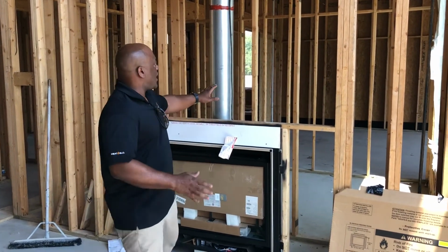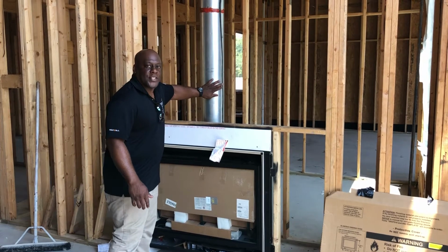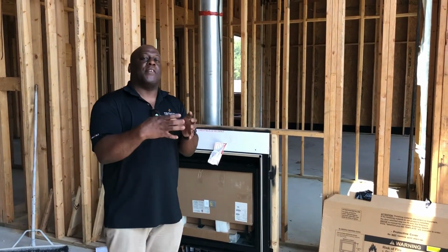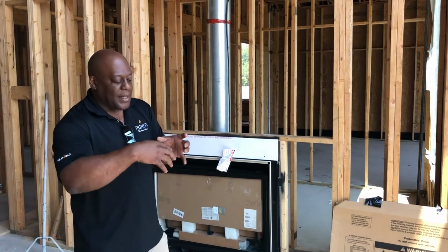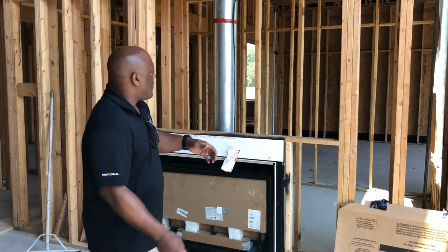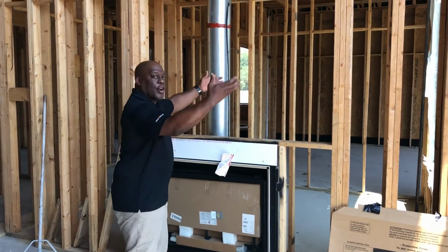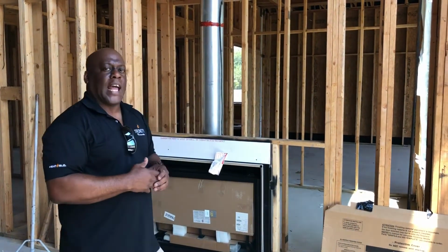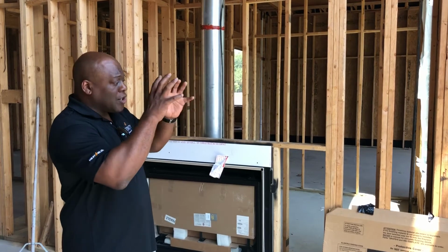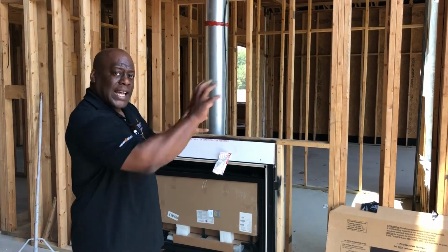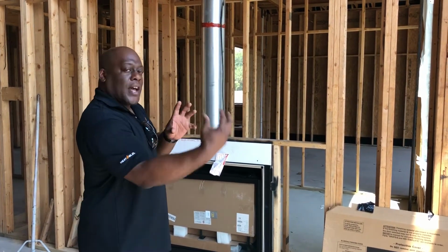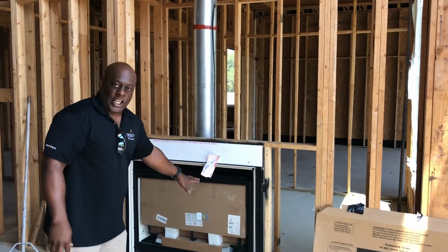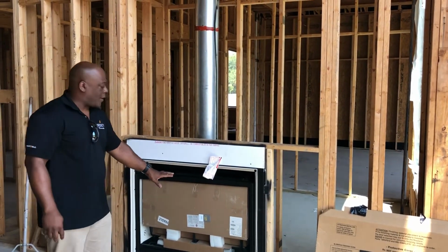So that means what we see here is an 8-inch pipe on the outside. But there's also another pipe on the inside, a 5-inch pipe. That 5-inch pipe is exhausting gases, and this outer pipe here is actually bringing in fresh air from outside. So that termination cap we looked at before actually has two openings. One opening is letting the gases out. The other one is bringing fresh air in to supply ignition in the fireplace, to keep the fire going.